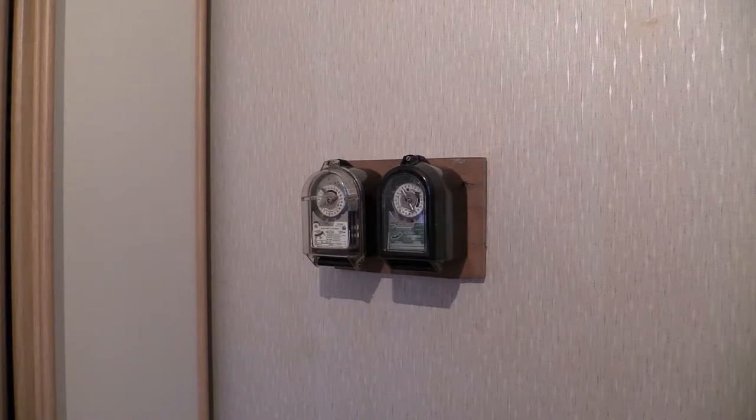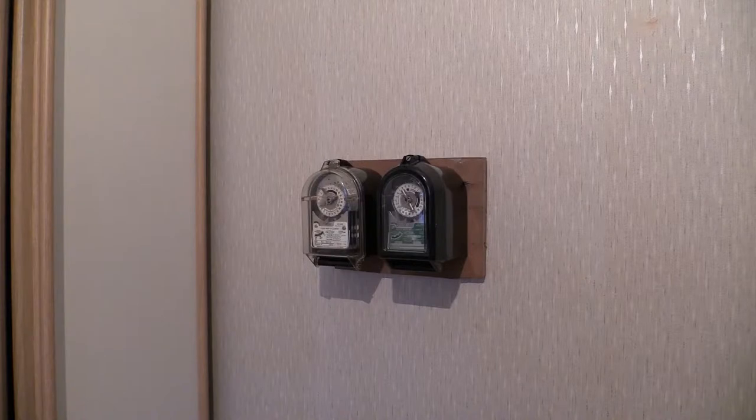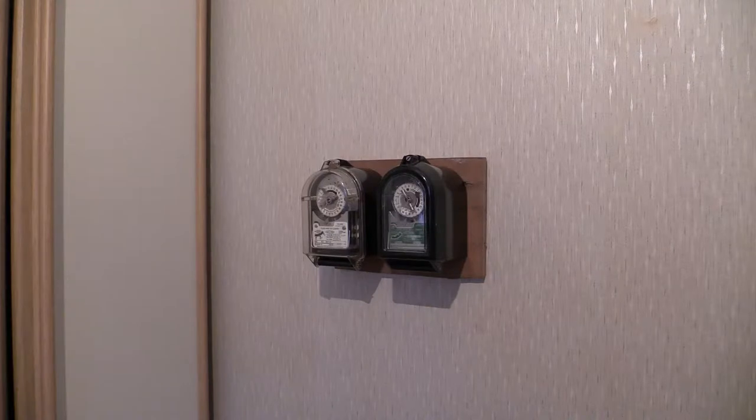And for the auxiliary contact, which is associated with the rate change, it's 2 amps. The synchro motor in these requires 200 to 250 volts, and the most important bit of course is the alternation frequency at 50 Hertz in order to get it to run at the correct speed.